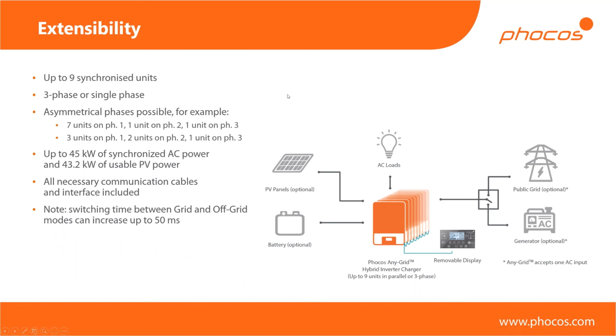Really, the only important thing is that you can have up to 9 units hooked together, so not more than 9. And that you must have at least 1 unit per phase. So if you're working with a single-phase system, of course, you can go from 1 to 9 units. And if you're using a 3-phase system, you need to have at least 1 on each phase. So obviously, you need to have at least 3 units. All the necessary communication and interface cables are included with each AnyGrid, so there's no need to order anything special if you want to have systems with multiple synchronized units.